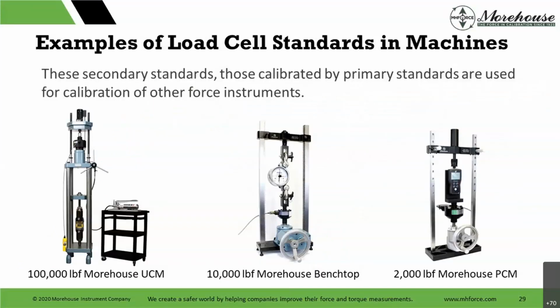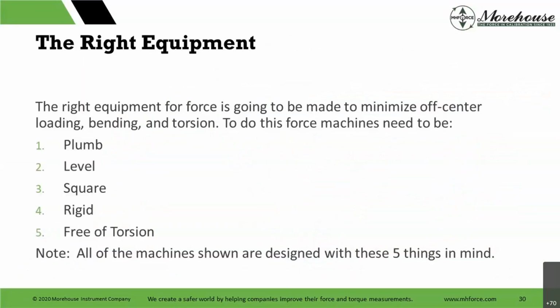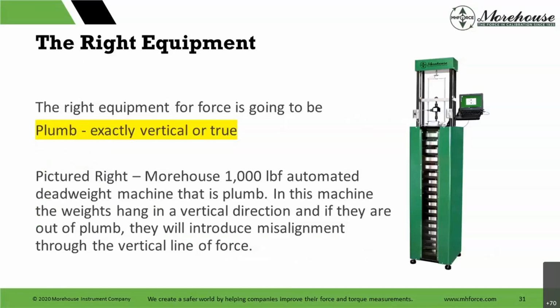Examples of load cells in machines. Here, again, there's our UCM, there's a benchtop, there's a PCM. Just really easy. The primary standards calibrate these standards. These standards are then used to calibrate other instrumentation. So the right equipment for force is going to minimize off-center loading, bending, and torsion. To do this, force machines must be plumb, level, square, rigid, and free of torsion. So all of the machines are designed that way.